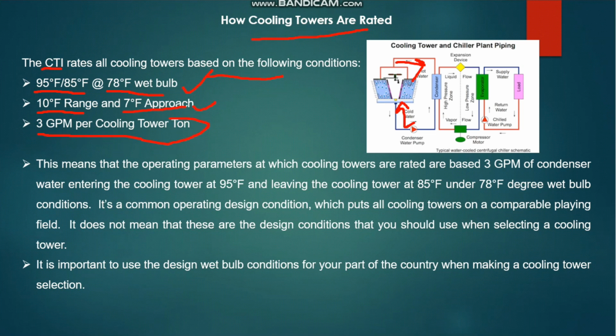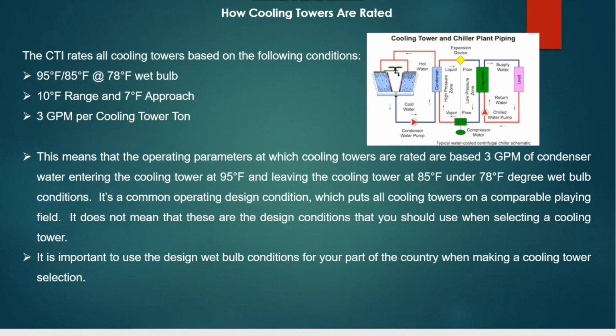And 3 GPM per cooling ton for the open circuit. As I explained, this is for the open circuit. We are using 3 GPM per ton for the open circuit. So this means 3 GPM of condenser water entering the cooling tower at 95 degrees Fahrenheit and leaving the cooling tower at 85 degrees Fahrenheit at 78 degree wet bulb temperature. That is the ambient wet bulb temperature. So it is a common operating design condition which puts all the cooling towers on a comparable playing field.